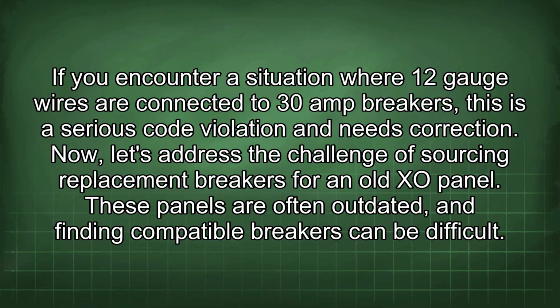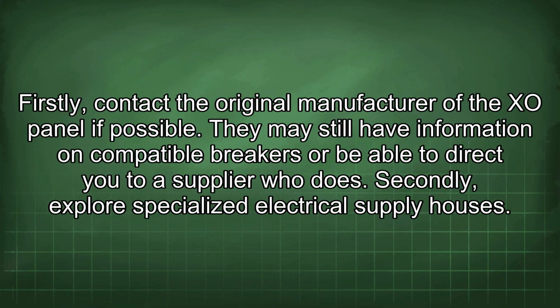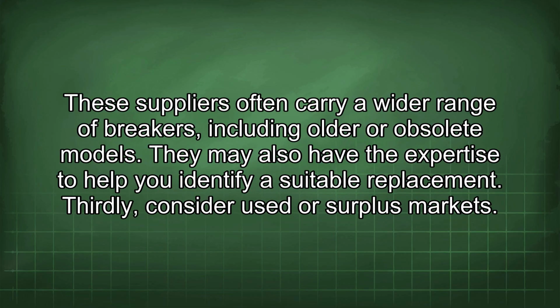Now, let's address the challenge of sourcing replacement breakers for an old XO panel. These panels are often outdated, and finding compatible breakers can be difficult. Firstly, contact the original manufacturer of the XO panel if possible. They may still have information on compatible breakers or be able to direct you to a supplier who does. Secondly, explore specialized electrical supply houses. These suppliers often carry a wider range of breakers, including older or obsolete models. They may also have the expertise to help you identify a suitable replacement.